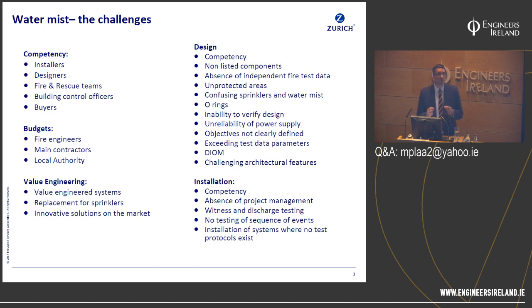So it's important to understand the objective of that water mist system. What are you trying to achieve? If it's a partial system, it cannot be a property protection system. It can only be there for means of escape, for prevention of flashover, lowering compartment temperatures. So be careful, be tenacious, and ask what the objective of that system is.